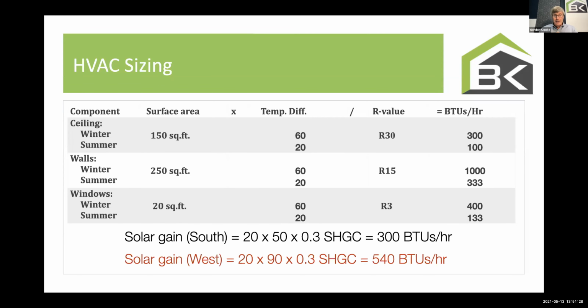Let's turn it west. And now that window is 540 BTUs. You can see why we're not that worried about attic insulation and what the temperature in the attic is. Boy, choose a good window, 540 BTUs on a west face. You can also start to imagine heat loss, heat gains. I wonder if I should be doing lot specific. If I'm building the same house in 4 different orientations, I probably want to do lot specific. Is it going to change the size of an air conditioner? Some of the houses you guys are building, it could change the size of the air conditioner. And that might be a cost savings, might also be a comfort. That's something you're going to have to think about.